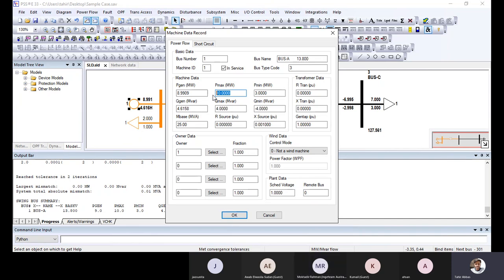Those who design the generator provide you with a generator capability curve of that generator. The operator can only run that generator within this range. If we move out of this range, then there will be an excitation loss of synchronism as well as a heating effect that will negatively impact the generator life.